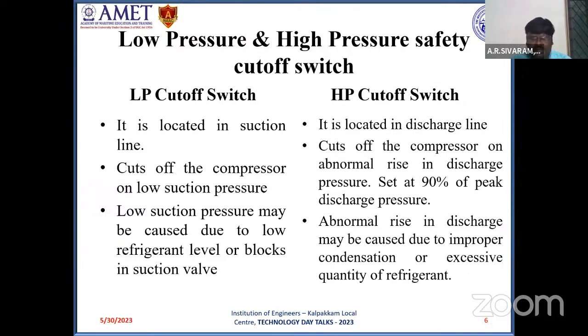Coming to the next switch, the high pressure safety cutoff switch, it is present at the discharge line of the compressor, that is, on the compressor outlet line. Normally any compressor has a maximum pressure limit that it can withstand. Once we cross the maximum pressure limit, the compressor is likely to explode. So the high pressure safety cutoff switch protects the compressor against very high discharge pressure. Normally, it is set at 90% of the peak pressure that the compressor can withstand. Once the real-time discharge pressure reaches 90% of peak pressure, the high pressure safety cutoff switch trips off or cuts off the compressor, thereby protecting it from getting damaged.